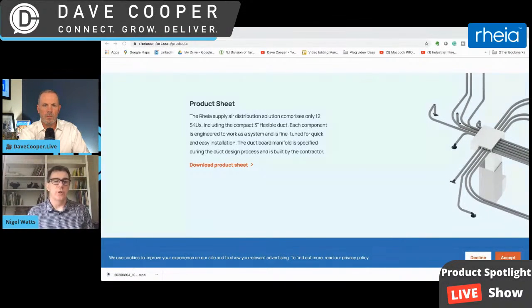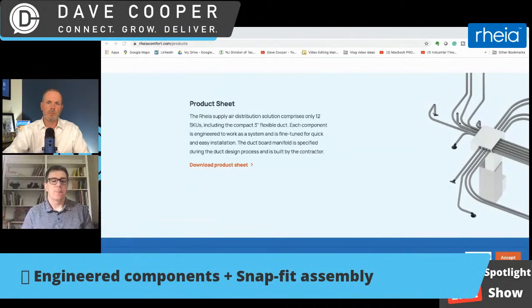Early on we worked for a couple of years with Carrier, and they helped steer us in the right direction to make sure it would perform within a particular band of static pressure. That static pressure is important to the manufacturer, because if you exceed it in performance, you wear out the equipment much faster, and that probably even creates a warranty issue. So we stay within that range, and that's what's unique to us versus a high velocity system.